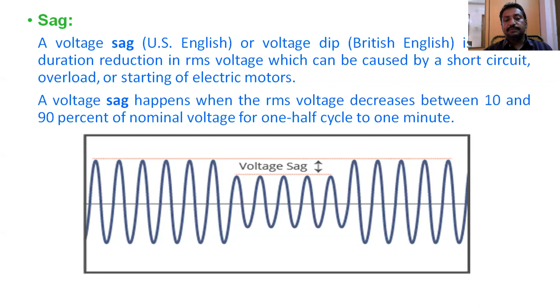Sag. In the USA people name it sag, and in British usage, both are the same. What is the meaning of sag? There is a decrease in the voltage in the electrical equipment due to a short circuit, overload, or starting of any electric motors. A sudden decrease in the voltage is called sag, or also a voltage dip. A voltage sag happens when the RMS voltage decreases between 10 and 90% of nominal voltage for half a cycle to 1 minute.